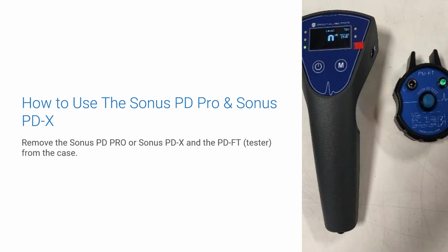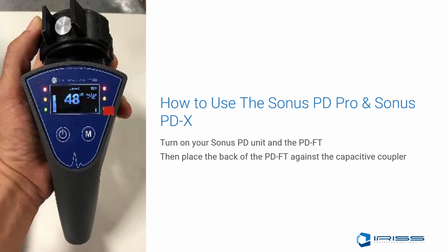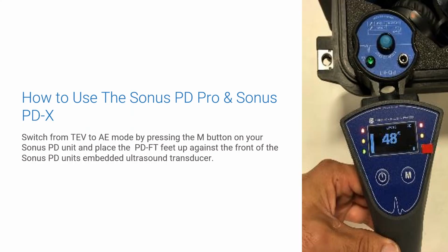Now let's go through how to actually use the Sonus PD Pro or Sonus PDX. First, you'll need to remove the device from the case, as well as the PDFT tester. Next, power your Sonus PD Pro or Sonus PDX and the PDFT and place the back of it against the capacitive coupler. Switch from TEV to AE mode by pressing the M button on your Sonus PD unit and place the PDFT feet up against the front of the Sonus PD unit's embedded ultrasound transducer.